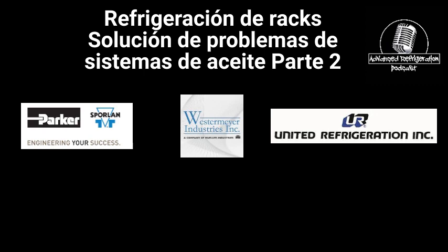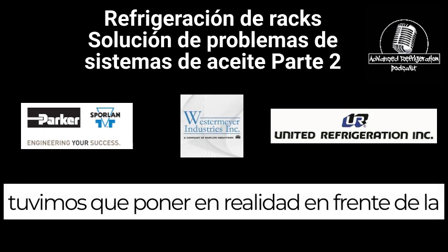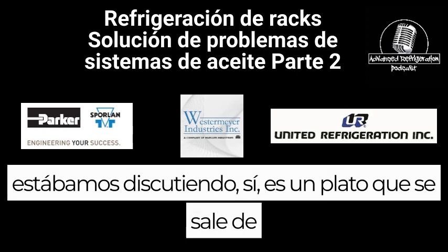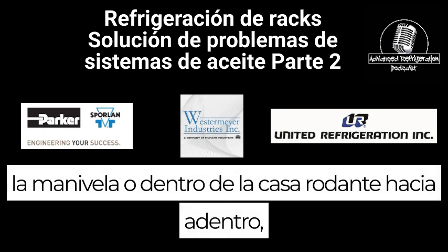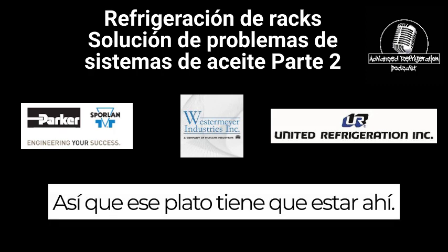Yeah, there are some compressors where we actually had to put a plate in front of the oil level control on a couple of them. It's a plate that goes on there that blocks the hole and extends out the rod, because the oil inside the crankcase, inside the motor housing, is so volatile that it trips on low oil level. It actually looks like there's no oil in there, but there actually is oil. Yep, it causes it to keep filling because it thinks there's no oil. So that plate has to be in there.